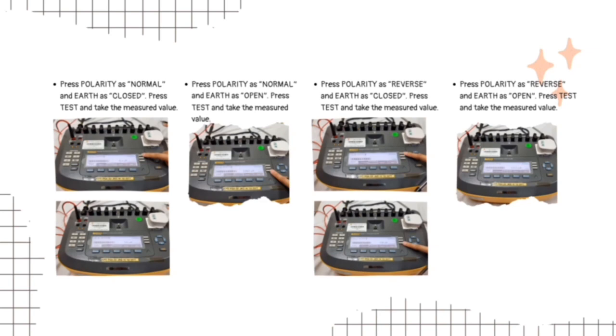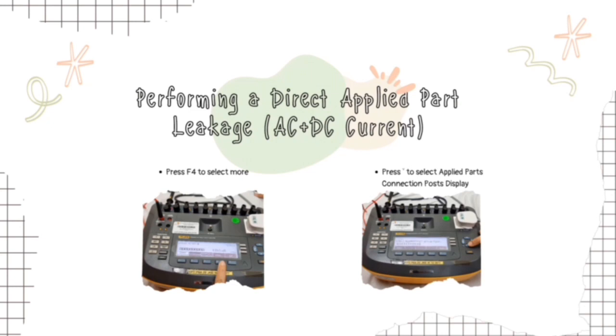And then we must change the polarity as reverse and earth as closed, and again press test to take the result. Then press polarity as reverse and earth as open, then test to take the measured value. Next is performing a direct applied part leakage AC plus DC current.